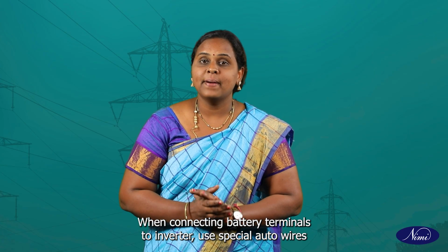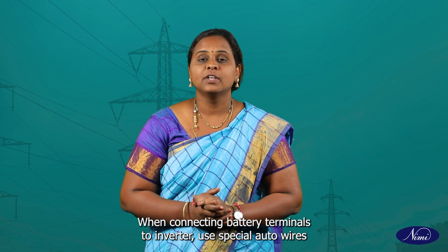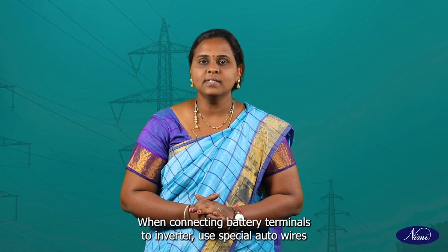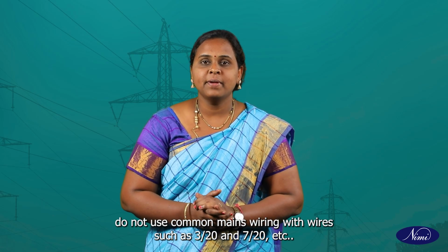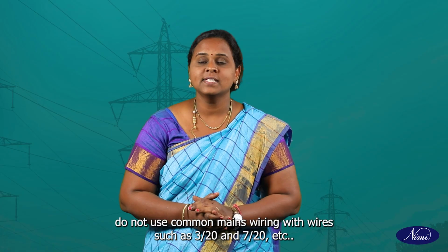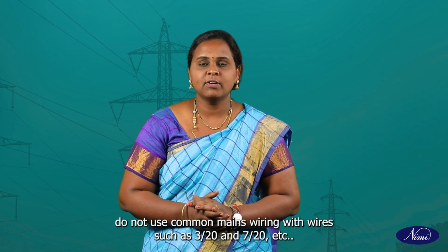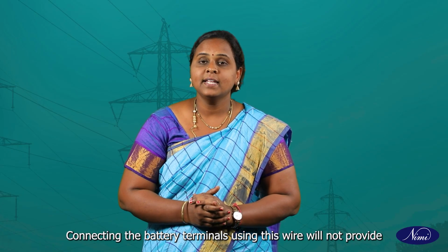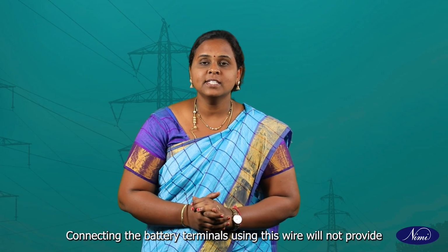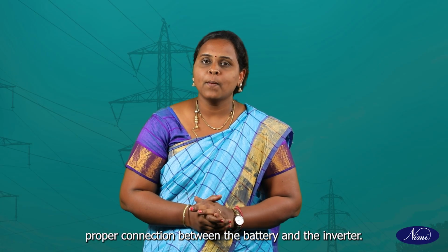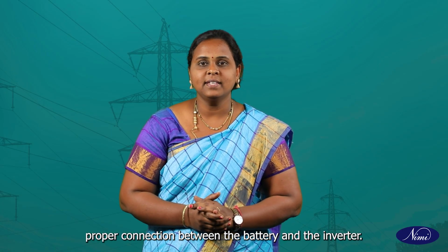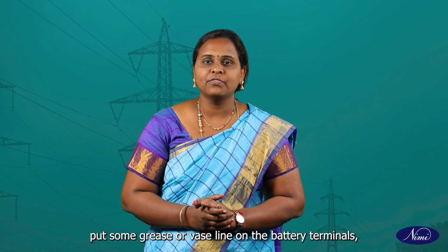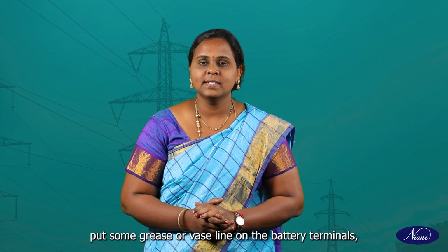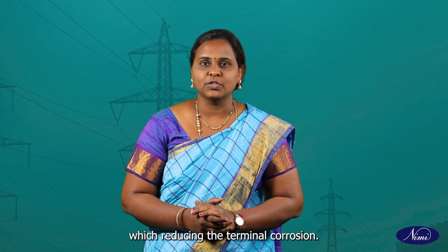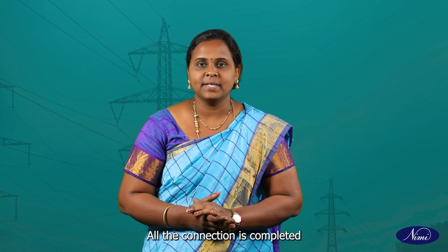When connecting battery terminals to the inverter, use special auto wires. Do not use common mains wiring with wires such as 3x20 and 7x20 etc. Connecting the battery terminals using this wire will not provide a proper connection between the battery and the inverter. After connecting the battery, put some grease or vaseline on the battery terminals, which reduces terminal corrosion. All the connections are completed.